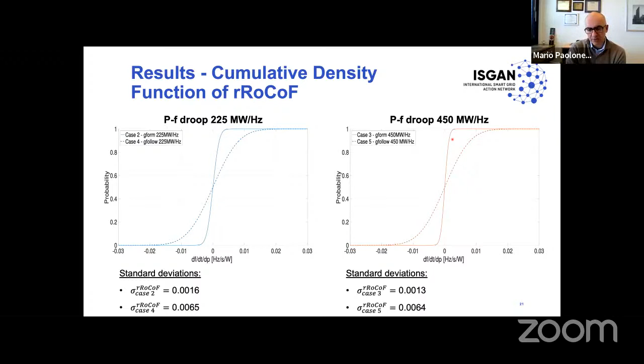The results are essentially the same as what we obtained experimentally on the EPFL campus. Here we are comparing the CDF of the average relative ROCOF across all 19 nodes of the grid: grid forming is the continuous curve, grid following the dashed curve. On the left is a P-f droop of 225 megawatts per hertz, and on the right a PF droop of 450 megawatts per hertz. The grid forming has a way stiffer CDF, meaning it's capable of maintaining the ROCOF per regulating watt of power way closer to zero, essentially stiffening the system response.